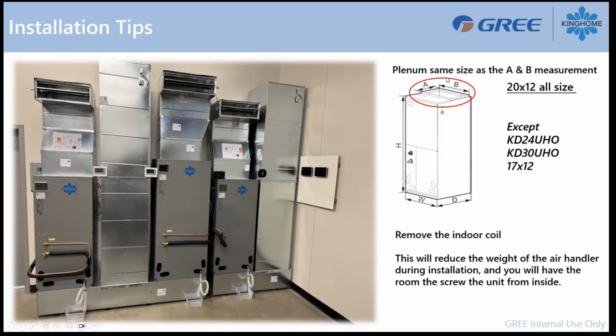Again, I put some notes here about the plenum size, the ductwork that you will install on the top of the air handler. So they are all the same size, like 20 by 12, except for the smaller tonnage, the smaller capacity of the KD, that will be 17 by 12.